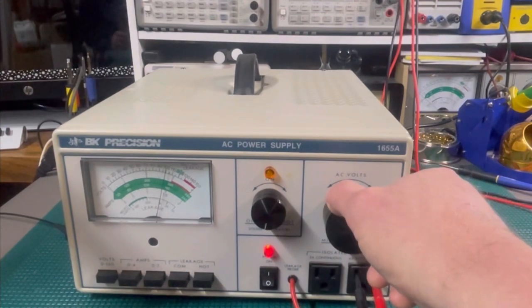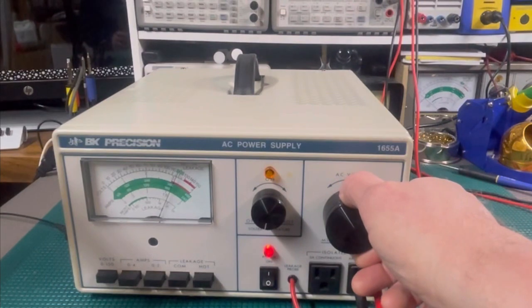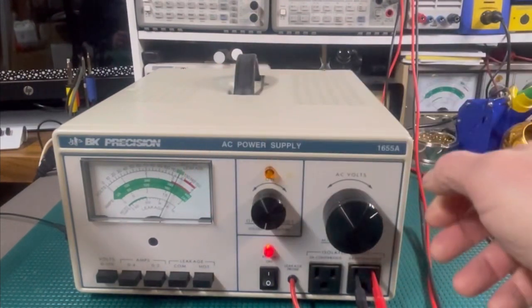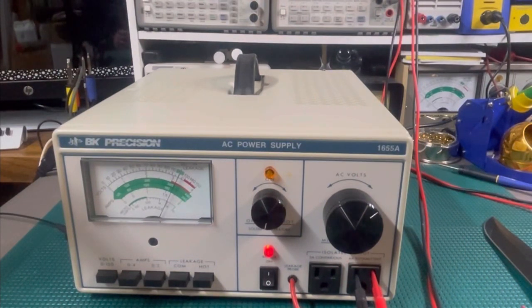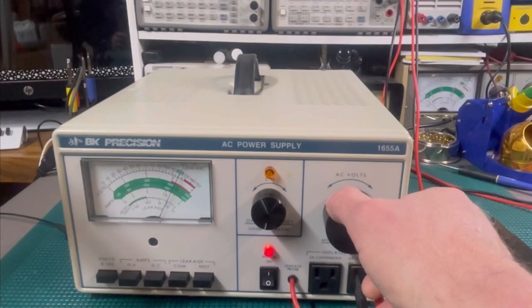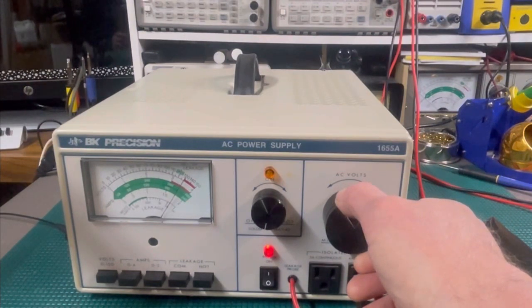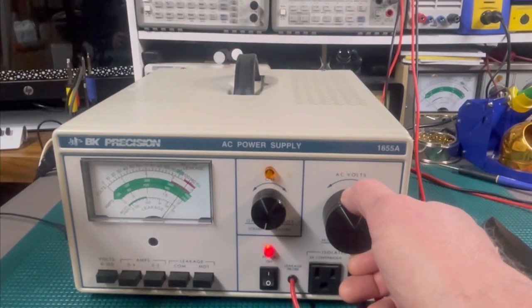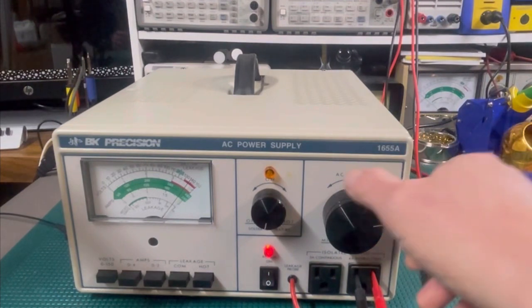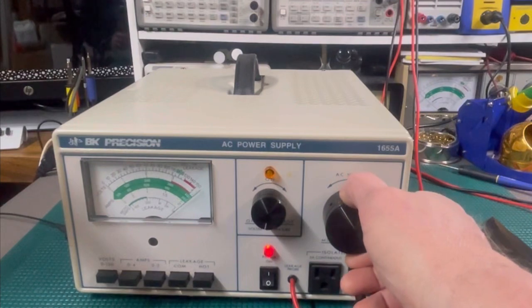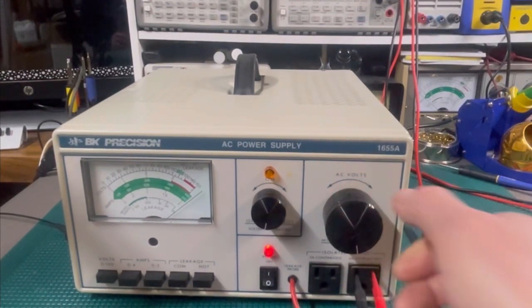Where it should be calibrated, and should be the most accurate, would be 120, since that's where all the printed, screened-on test measurements are for current, or for voltage leakage and amperage use on the gauge of the meter. Okay. And it says we're only putting out 104 at 120. We don't hit 120 until close to 140. So let's see if we can get the full 150 out of this. Okay, yeah, there we go. We can actually get 160.